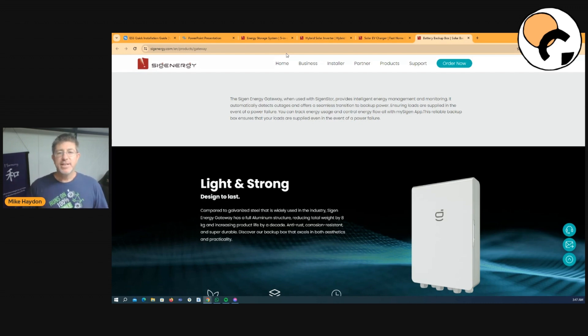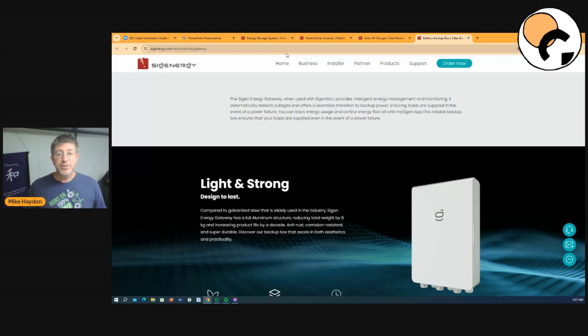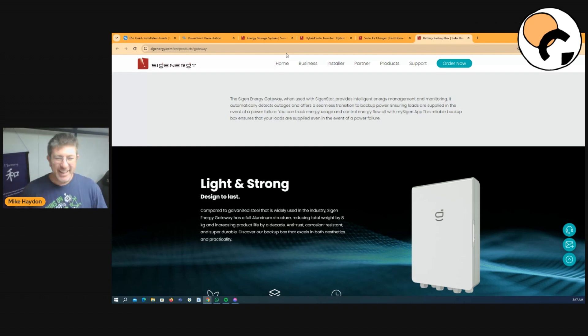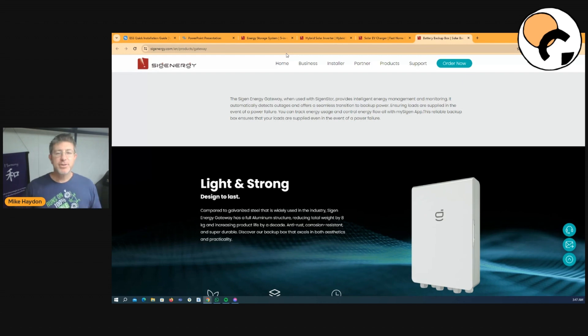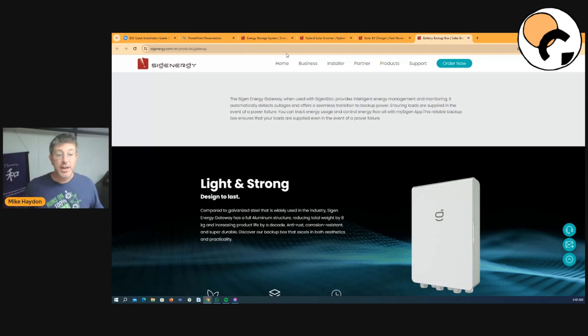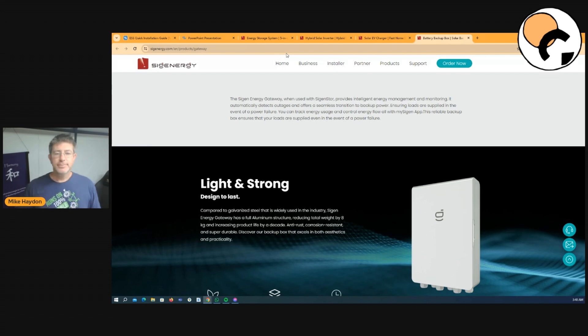Now, even with the battery technology, they've actually tested these lithium batteries all the way down to minus 25 degrees. And that's another thing that I've seen on with a lot of battery manufacturers here in Australia. There are certain batteries in Australia that their warranties are void the minute we install them because they're not meant to go over 40 degrees ambient temperature. And that's potentially every day in Australia. There's some locations in Australia that the ambient outside temperature of a battery is going to be 40 degrees because it's not just about the temperature of the outside environment. The battery itself is going to create heat, the external heat from the outside is going to help push that battery temperatures up. And there are batteries sold in Australia right now. The battery warranty is pretty much void unless you're installing it in Tasmania.